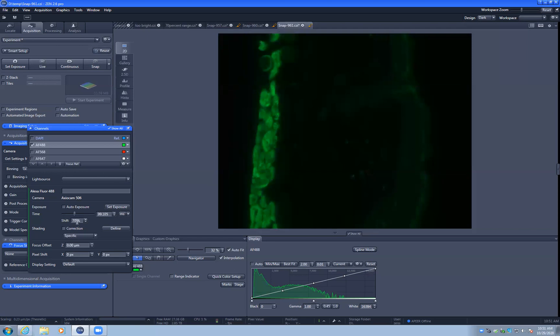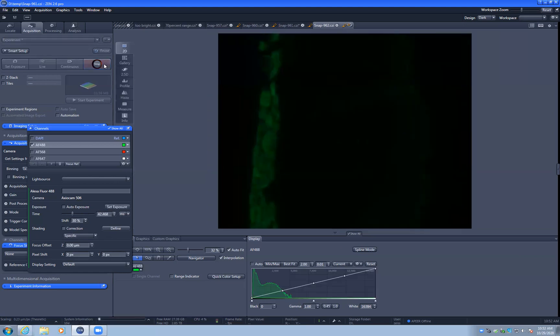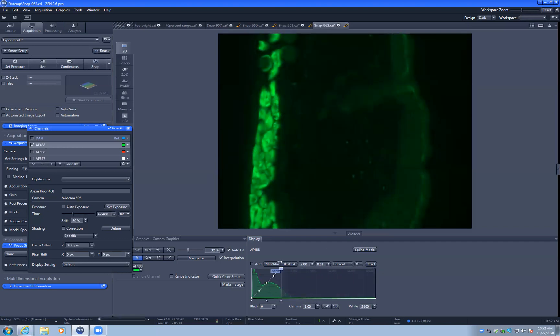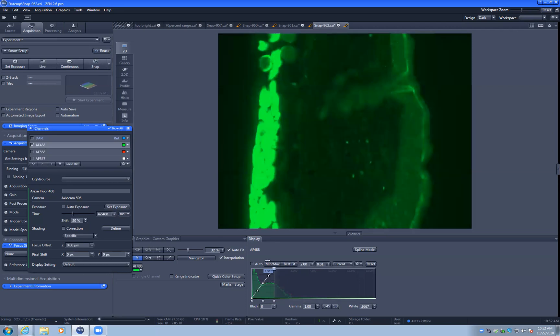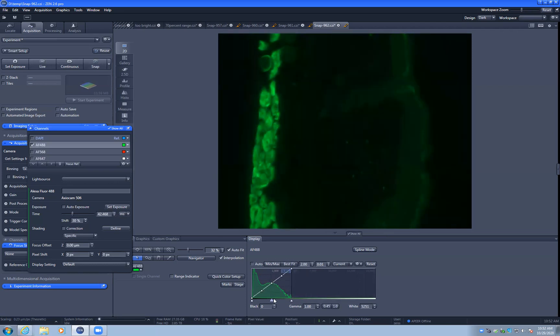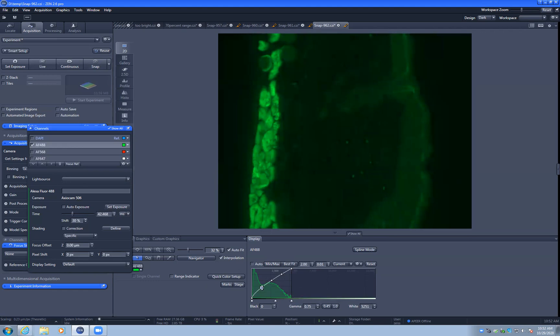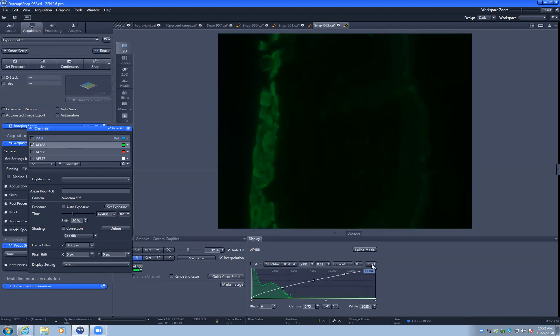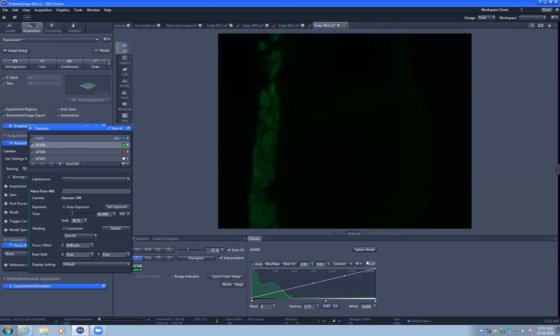If you had a bleaching problem, you might say, well, instead of using 70%, you can use 30%, because the camera is so low noise, and if we didn't have this differential, if we only had the pixel values on the right, we actually wouldn't need such a long exposure. We don't have to fill the range. So we can go to 30% auto exposure, set exposure, and you can see in this picture, at 30%, it looks dim, but if we adjust our contrast afterwards, it still has great signal, because we actually don't need more than a thousand counts in order to get a really nice image. So if you have a bleaching issue, or for some other reason, you don't want to use long exposure. Maybe you're going to be tiling large areas, and actually trimming 100 milliseconds off each exposure over large areas can save some time. You actually have a very nice image without getting near saturation.